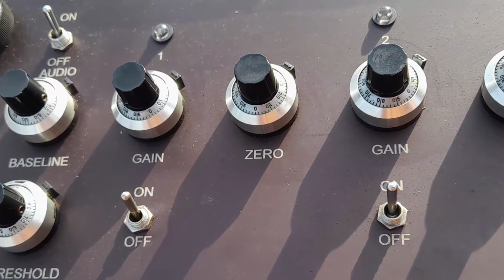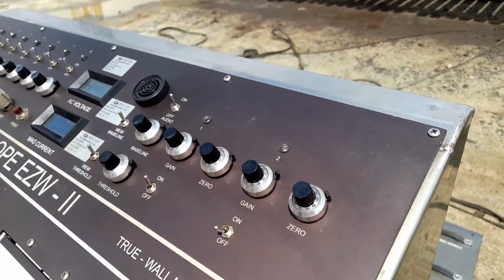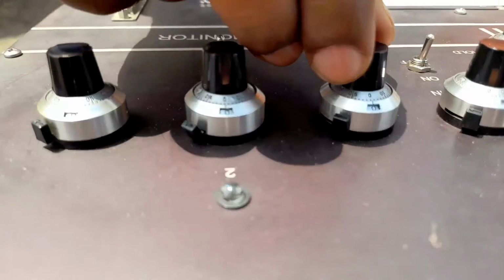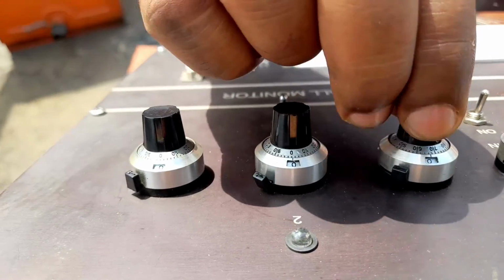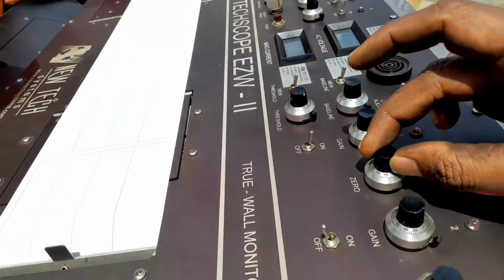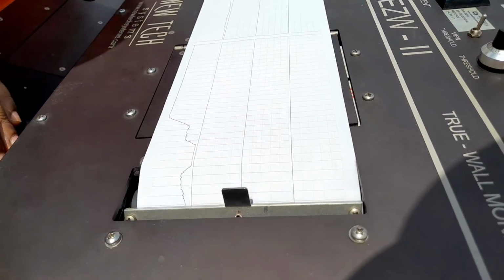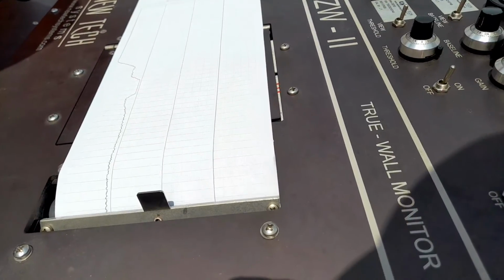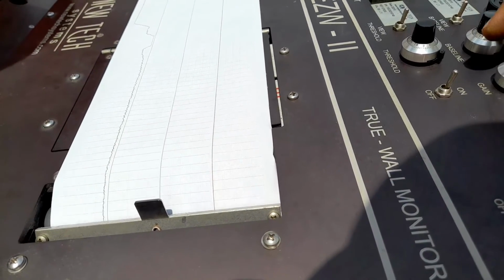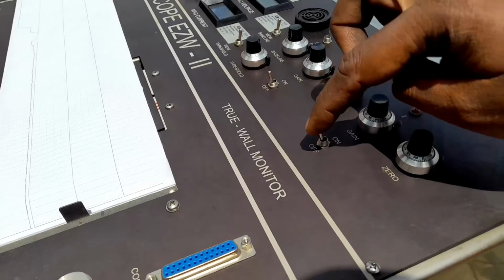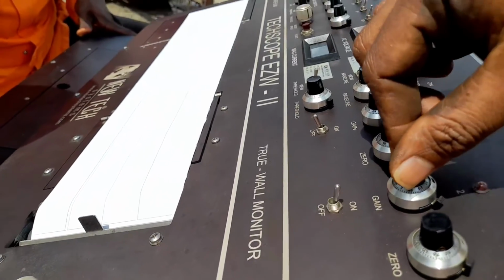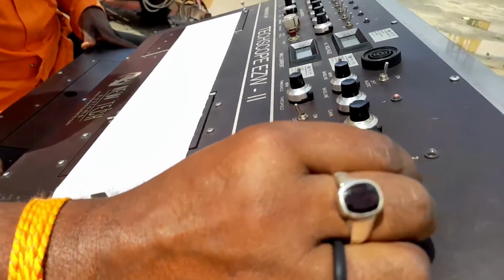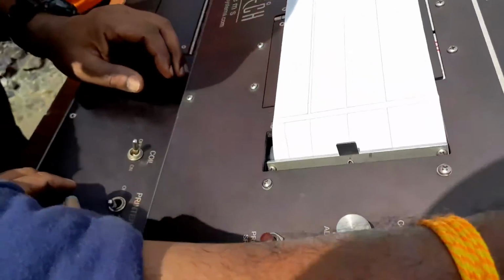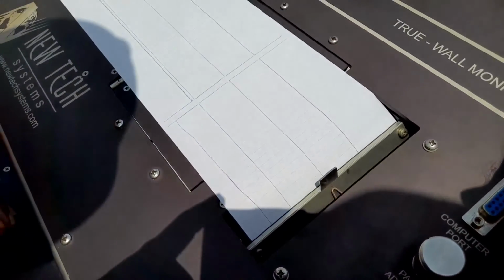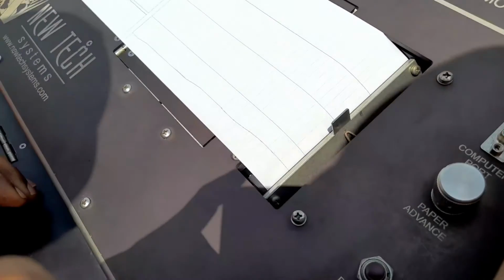First is switch on the wall monitoring section 1, then run the chart, adjust the zero and gain to get the wall loss kick, wall loss indication on graph. If you get it in the middle of the graph, the kick is not passing threshold, you have to adjust the gain. Repeat the same technique for the second section. Switch on the second one, run the chart, adjust the value. After completing both setups, you have to switch on both toggle switches and run it. You can get the value in the proper place. This is the first method.